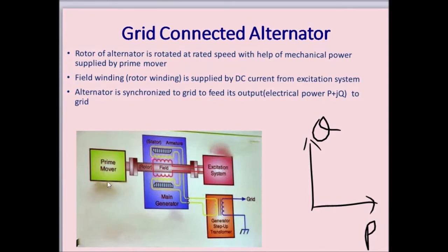This figure shows an alternator connected to the grid through a step-up transformer. The alternator carries a three-phase armature winding present on the stator, and that three-phase winding is generally star connected. This three-phase winding is connected to the grid through the step-up transformer, and the rotor of the alternator rotates at synchronous speed with the help of a prime mover. The rotor winding is supplied by DC current with the help of an excitation system.